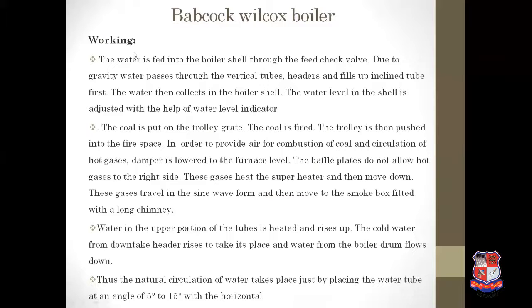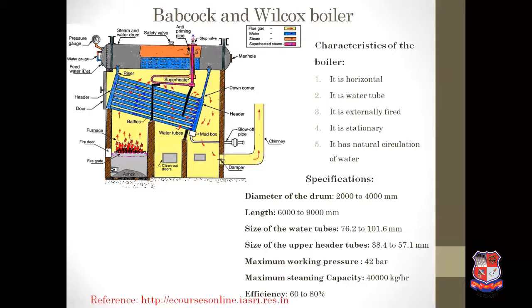Working of the Babcock-Wilcox boiler: water is fed into the boiler shell through the feed check valve. Due to gravity, water passes through the vertical tube headers and fills the inclined tubes first, then the water level in the boiler shell is adjusted with the help of a water level indicator. Water first fills the bottom area of the water tubes, then the headers, and finally the cylindrical shell space.